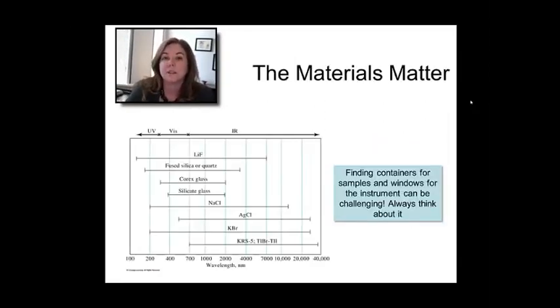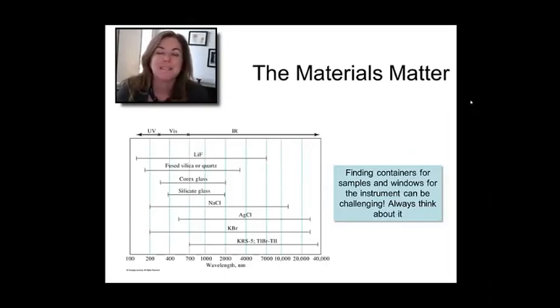Let's talk a little bit about the materials that make up the system. It starts with a simple decision, which is what do you put your sample in? And that's actually a really complicated decision for optical and infrared spectroscopy, because not every material is good. If you tried to do UV-vis spectroscopy in a glass cuvette, you would be blind to anything below 400 nanometers. So anything in the ultraviolet, where some of the best organic chromophores absorb, you wouldn't be able to see them because the glass would be absorbing that light.